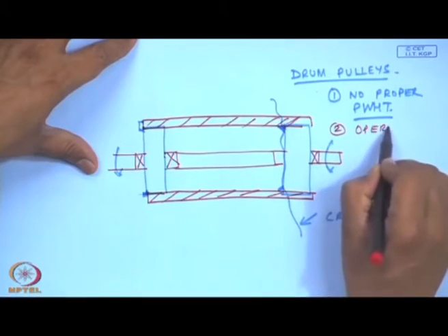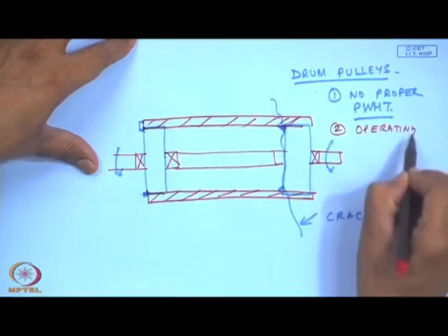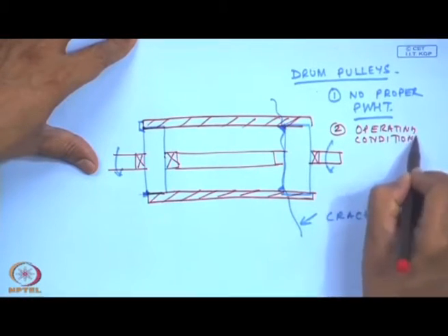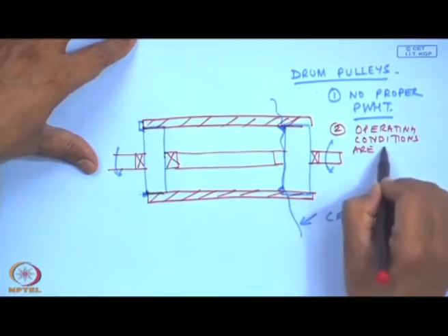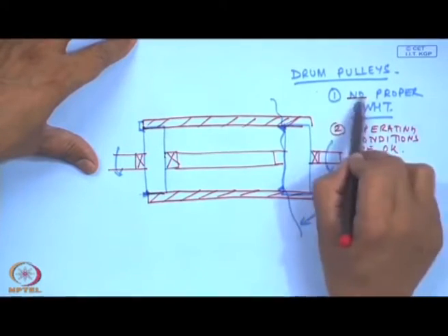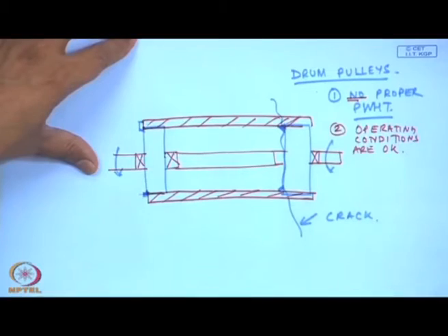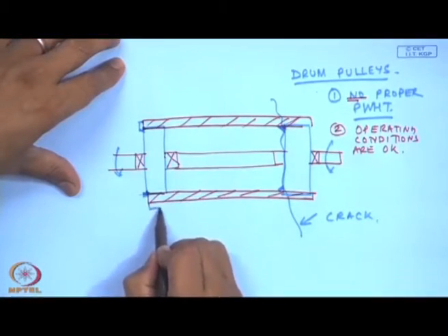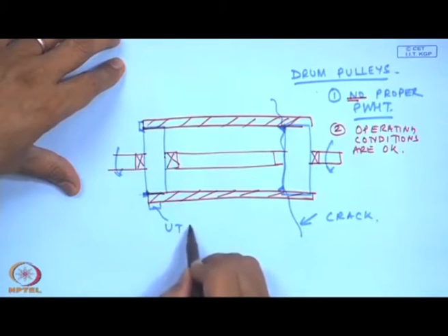Operating conditions are good enough. But because of no proper heat treatment, in such cases they recommend that a UT inspection is done.